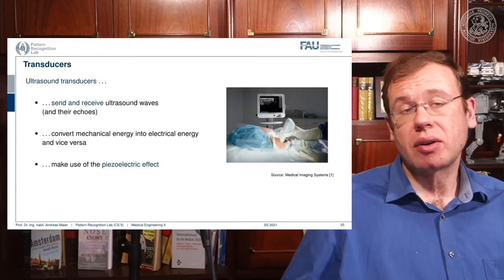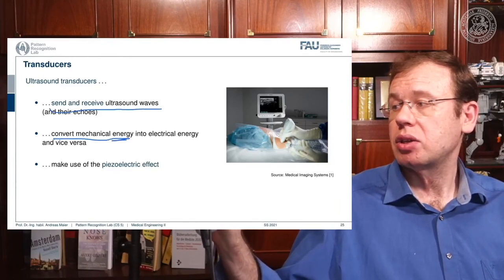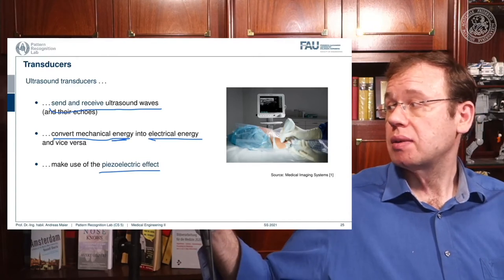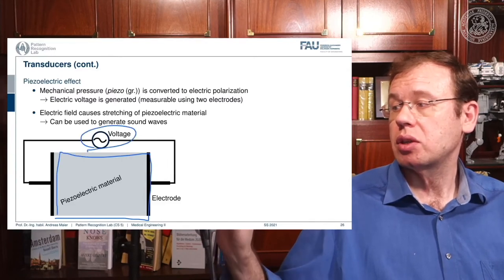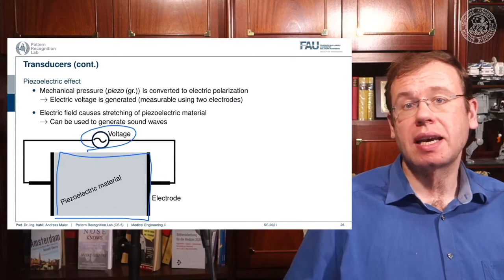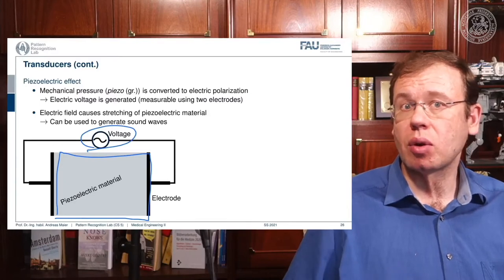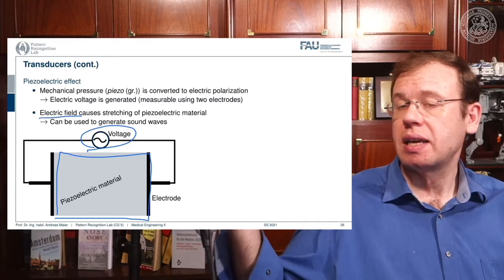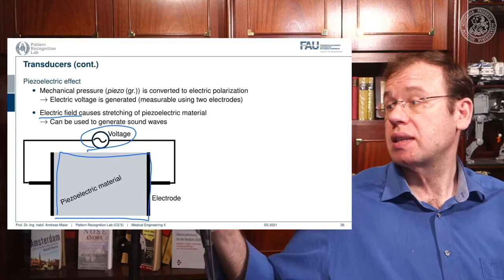Ultrasound transducers must send and receive ultrasound waves, converting mechanical energy into electrical energy and vice versa — this uses the piezoelectric effect. A piezo crystal, when a voltage is applied, expands almost instantaneously. By turning voltage on and off repeatedly, we create pressure waves. So we can convert an electric field into a pressure wave, and a pressure wave back into an electric field.